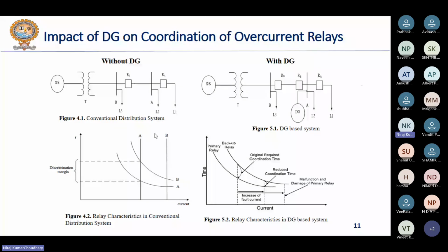Again, in slide number 11, we can see you have a radial system in which DG is not connected, and the same system where DG is connected at bus number A, or node A. For the first system, that is figure 4.1, suppose a fault occurs at any point after relay R1, before load L1, on this line. Then there should be a primary relay associated with that fault, and there should be a backup relay. If the primary relay fails to operate, then the backup relay should come into the picture. That's why in this time versus current characteristic, the IDMT characteristics, you can see that the time of operation for relay RA is below the time of operation for relay RB, right?